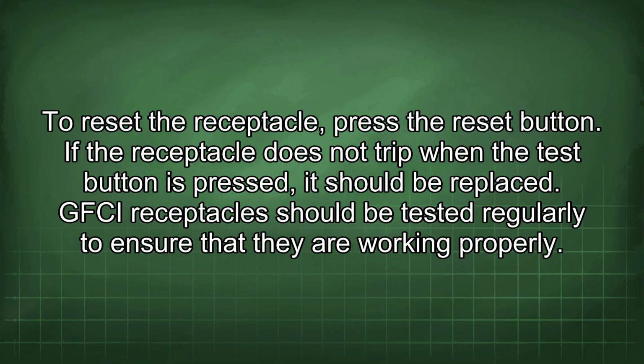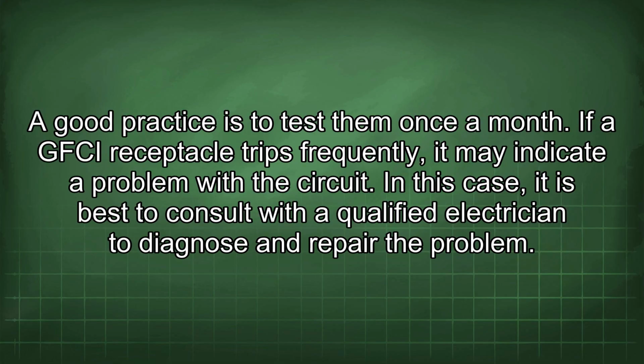GFCI receptacles should be tested regularly to ensure that they are working properly. A good practice is to test them once a month. If a GFCI receptacle trips frequently, it may indicate a problem with the circuit. In this case, it is best to consult with a qualified electrician to diagnose and repair the problem.